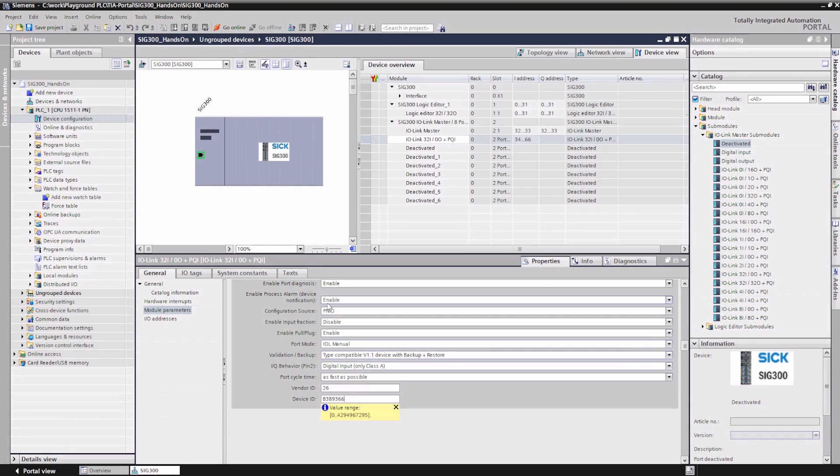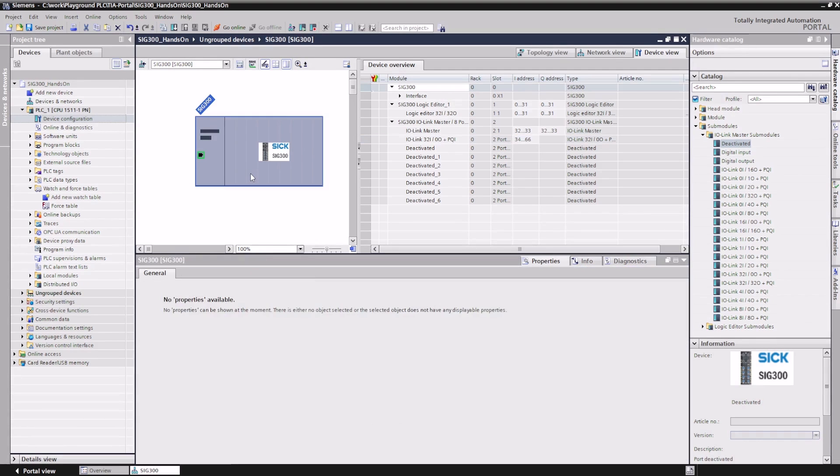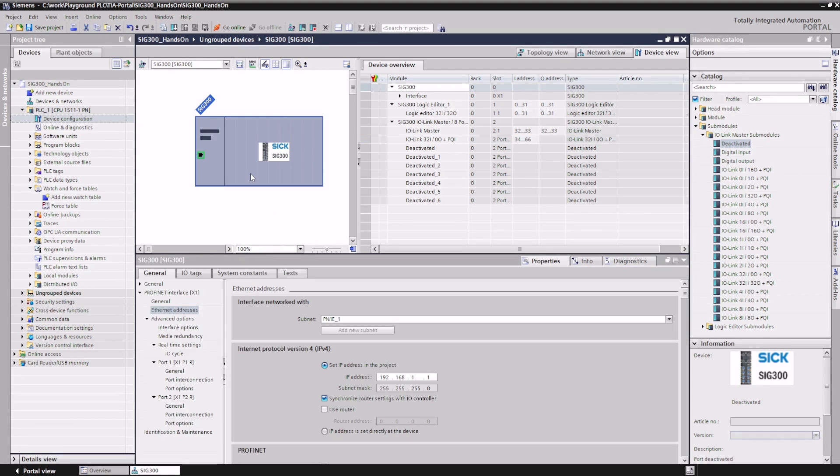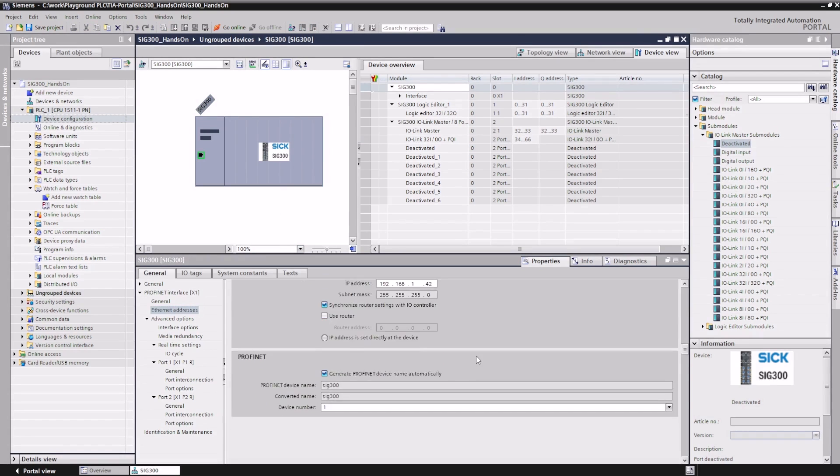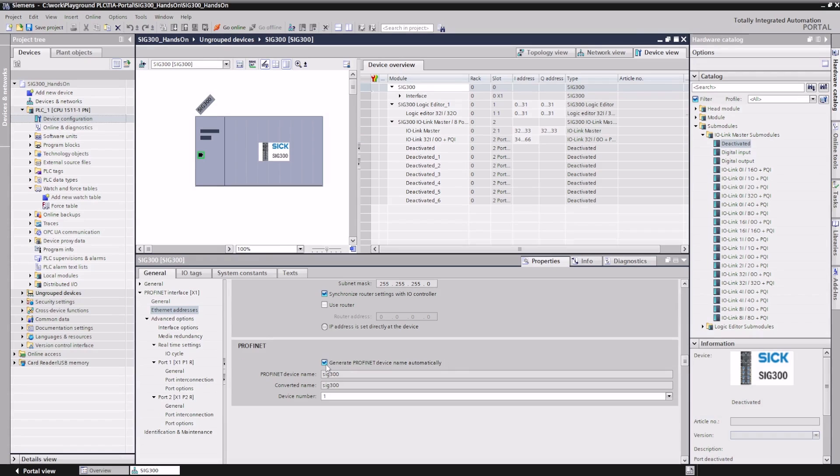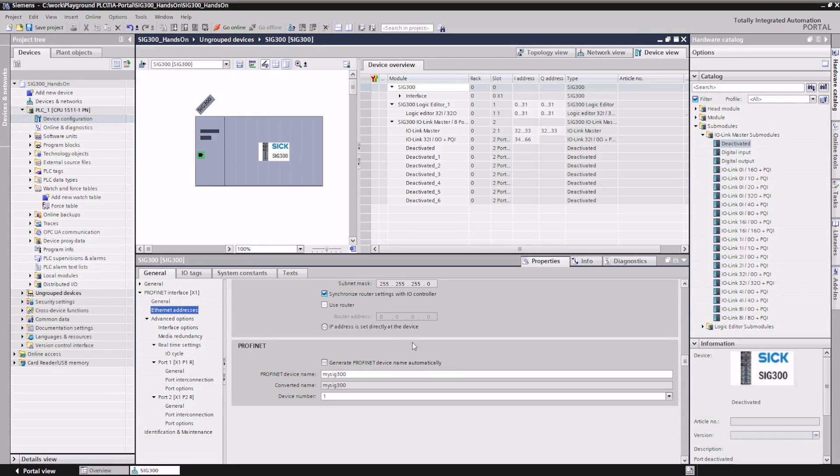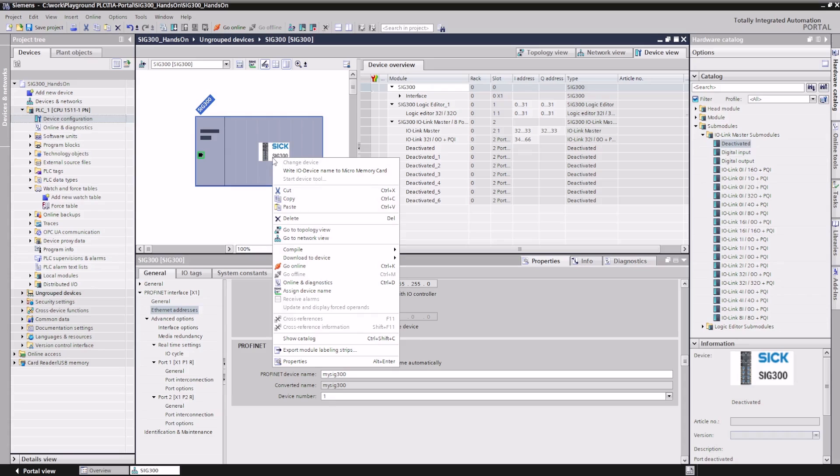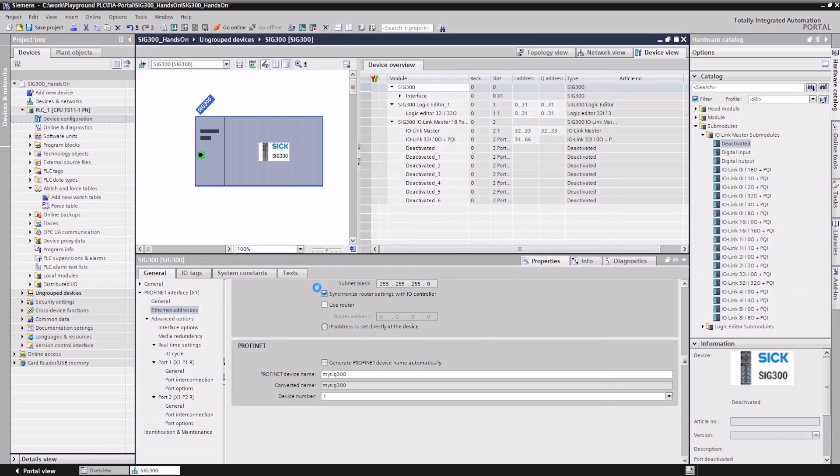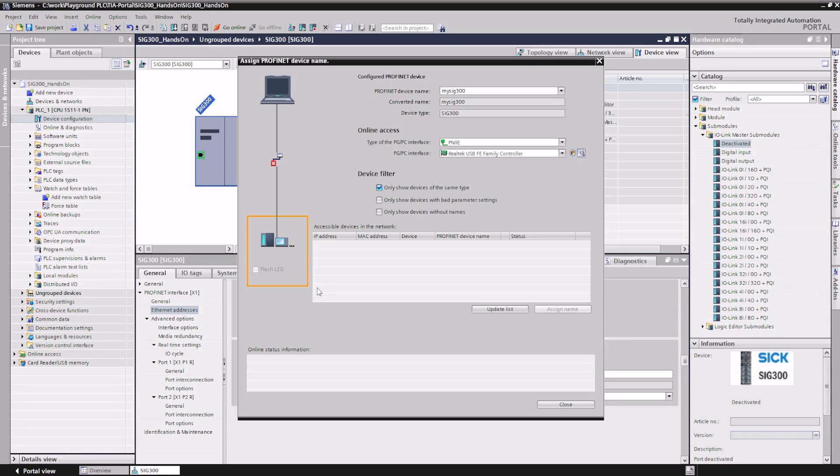The PROFINET name and the IP address that the PLC is to assign can be set up under Properties, Ethernet addresses. To assign the PROFINET name, right-click on the device plate and select the context menu, Assign Device Name. A window pops up which enables us to find the SIG300 PROFINET device in the network and give it the configured name.